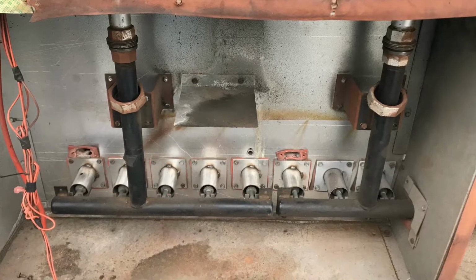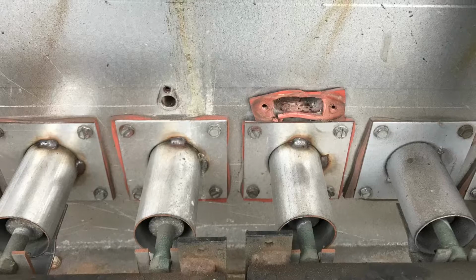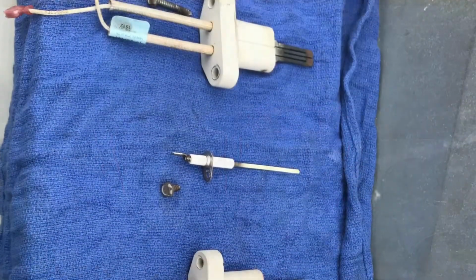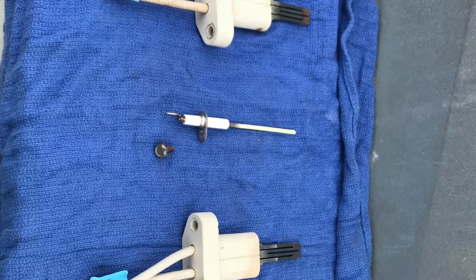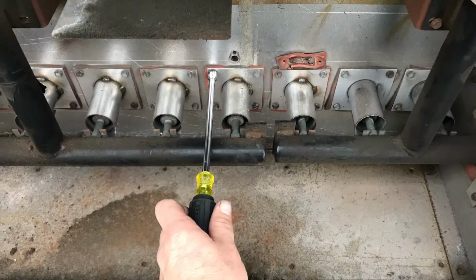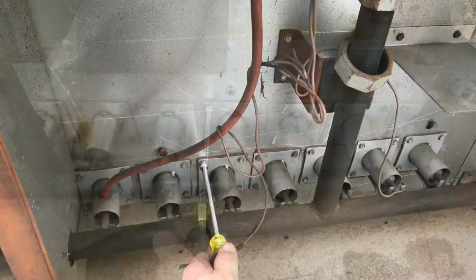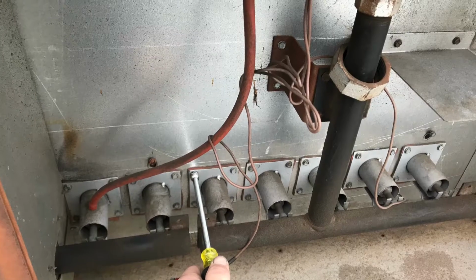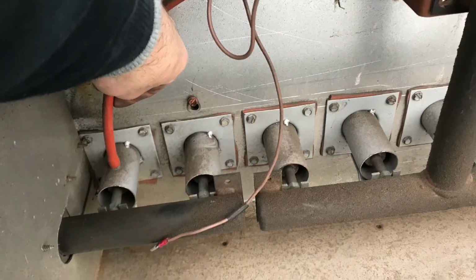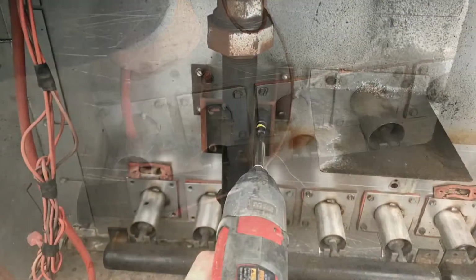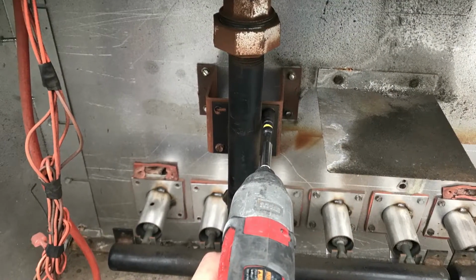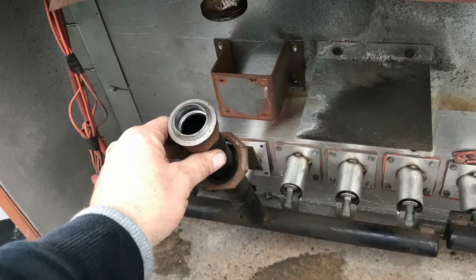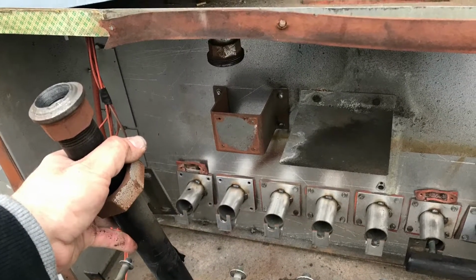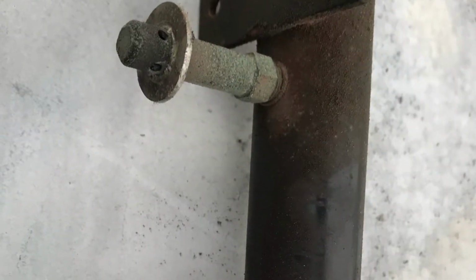Remove the unions, remove the flame rods and igniters. Here's the flame rods and igniters. Remove all the screws holding all the burners. Remove any wires or tubes attached to the burners. Remove the screws holding on the header. Remove the headers. This particular unit has 3 headers. And while the headers are off, inspect and clean the orifices. Now you're ready to remove the burners.